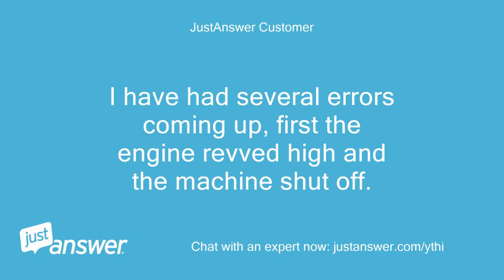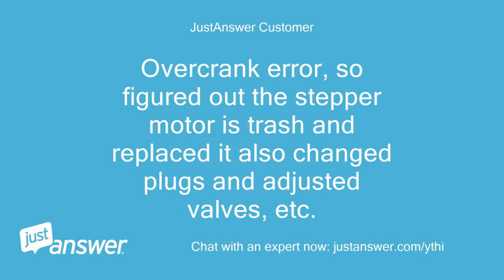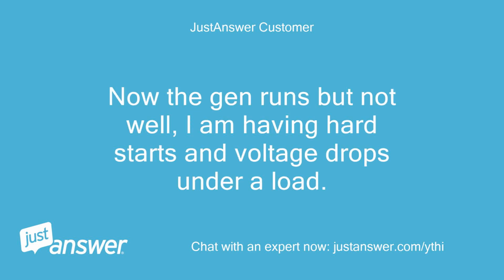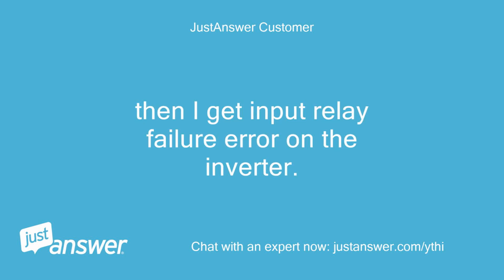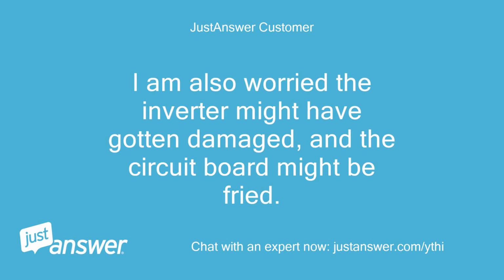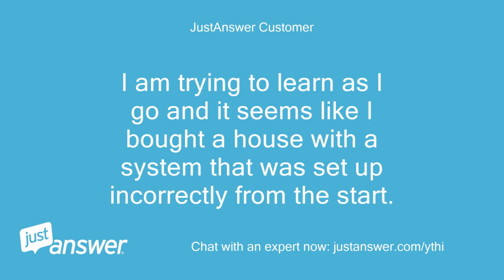I have had several errors coming up. First, the engine revved high and the machine shut off. Overcrank error, so figured out the stepper motor is trash and replaced it, also changed plugs and adjusted valves, etc. Now the gen runs but not well. I'm having hard starts and voltage drops under a load. Then I get input relay failure error on the inverter. I'm also worried the inverter might have gotten damaged, and the circuit board might be fried. I'm trying to learn as I go, and it seems like I bought a house with a system that was set up incorrectly from the start.